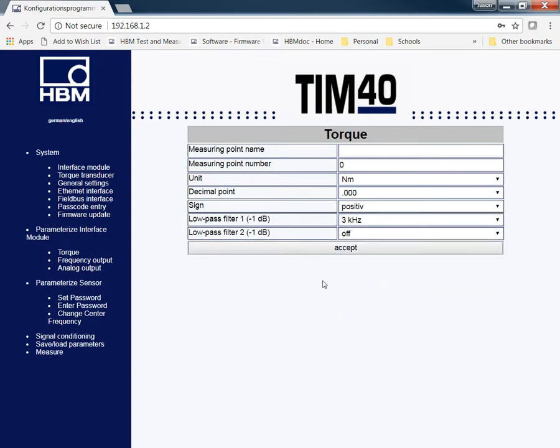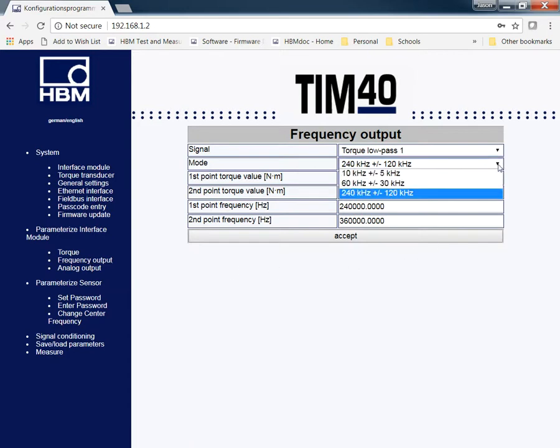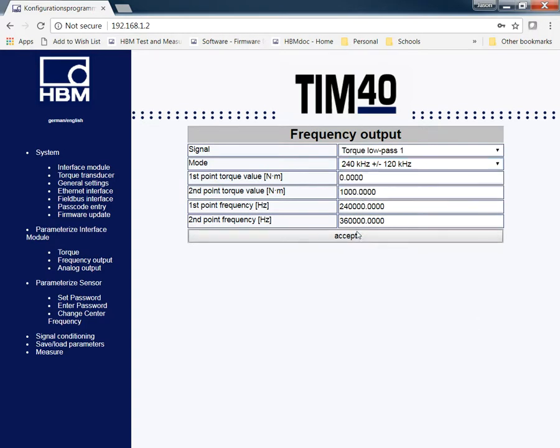I'm going to go to the frequency output. You can go through and parameterize this as well. Each of the T12s have different options you can change of what your center frequency is. This is where you change this. Right now, I've got mine set at 240 kHz is my zero value, and my top value, my top end is my 1,000 newton meters, is set at 360. You can go ahead and change this if you want, depending on what you're looking for for your input.